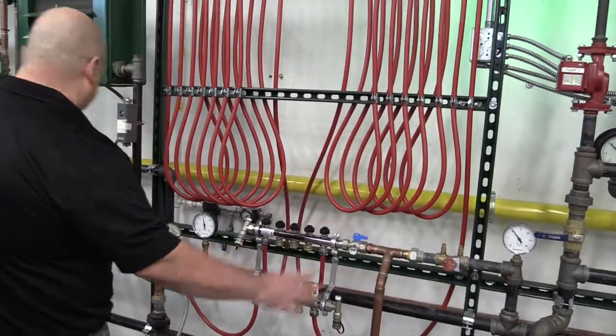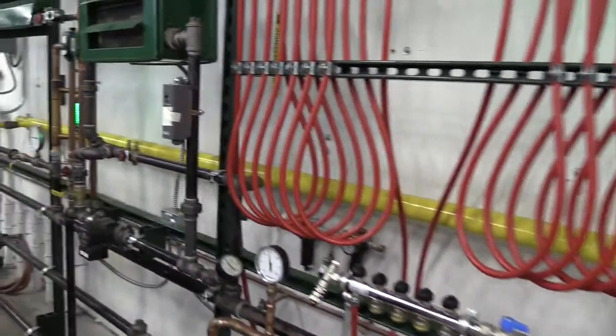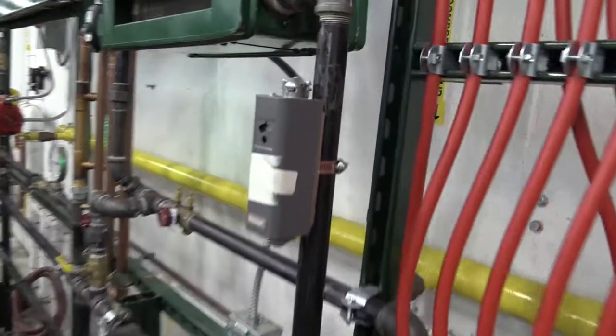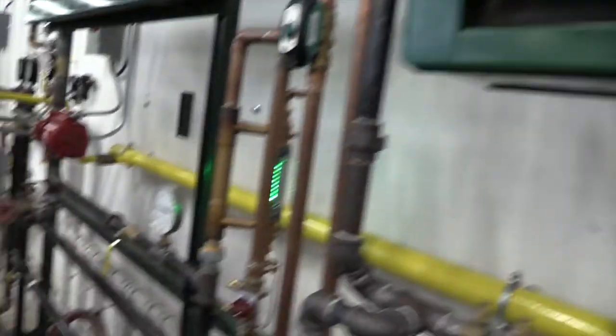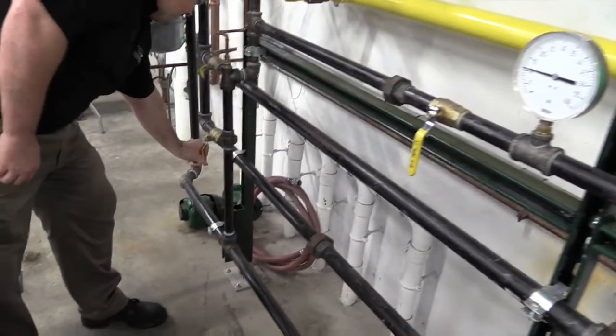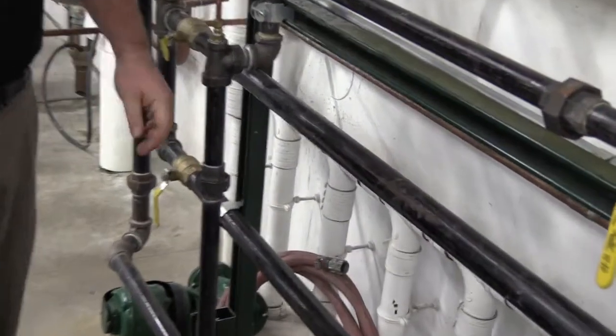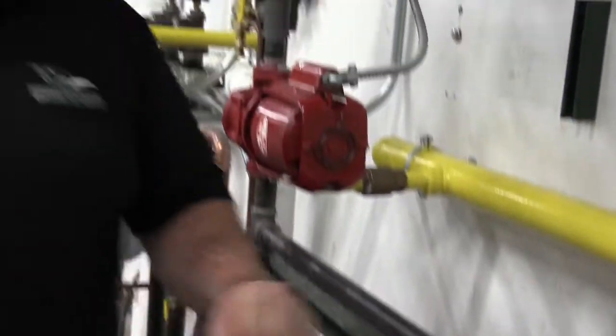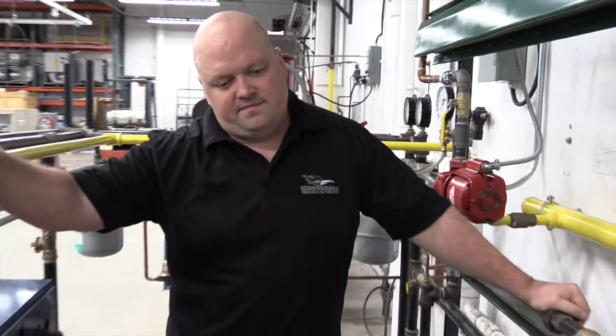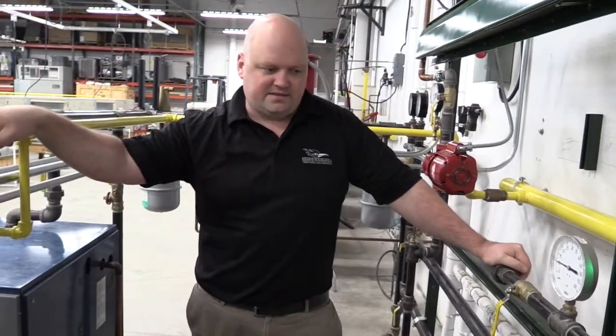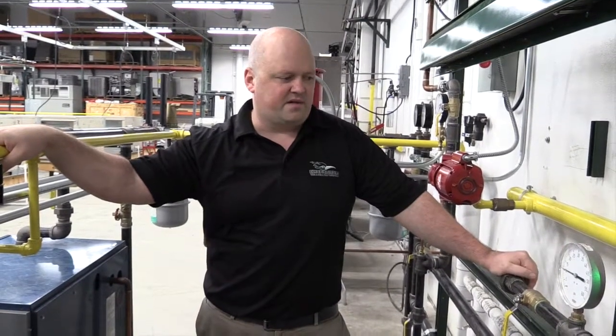Each one of these systems is a primary-secondary system that, with the flip of two valves, I can throw from direct to reverse return, and it changes all the flow characteristics. A lot of people like reverse return because it's almost like a self-balancing situation. The problem is that it doesn't really self-balance, so you still have to manage your flow.